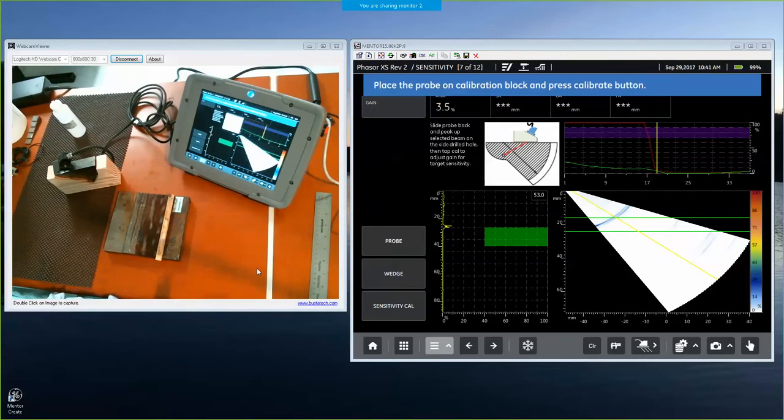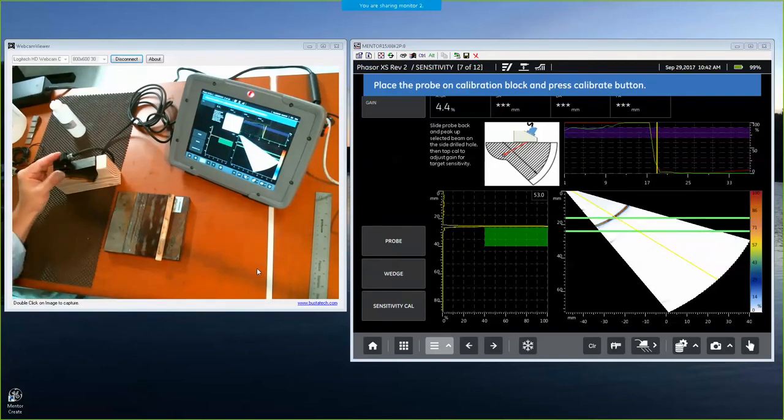So when you mentioned interpolation before, it's not exactly interpolation. We're going to add the same value to all beams, but velocity and auto 80 are done on the selected beam, while TCG and delay happen on every individual beam. Okay, before we go on, any other questions?